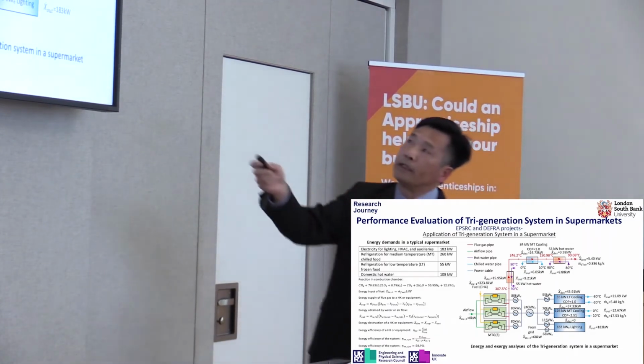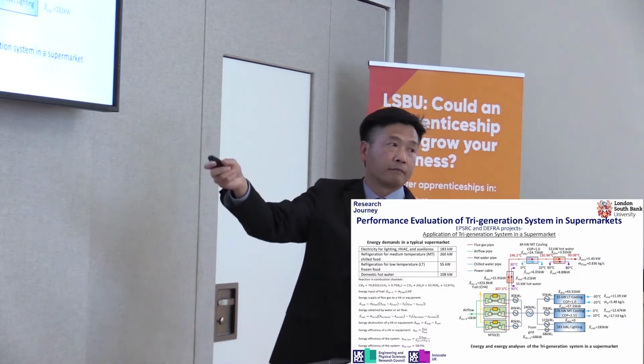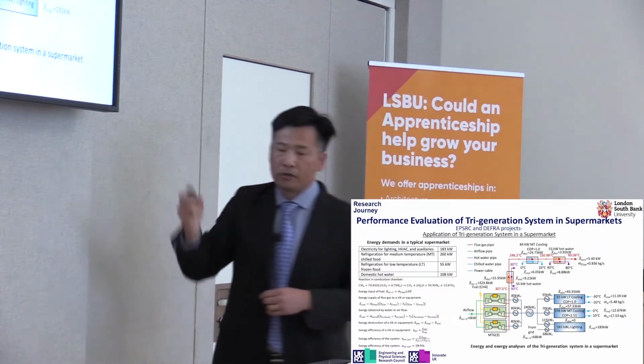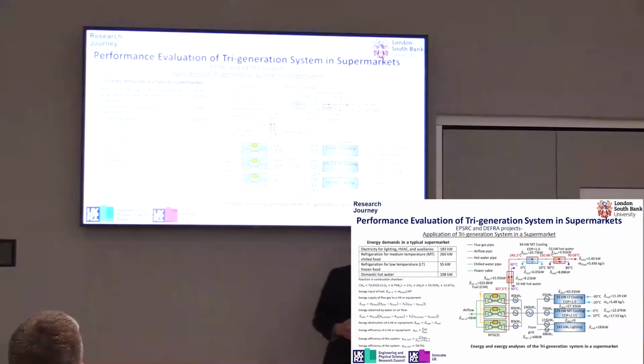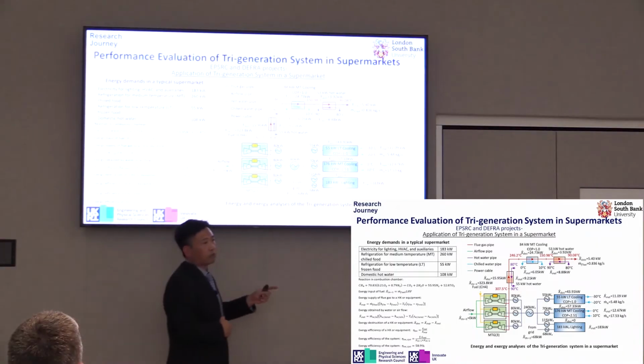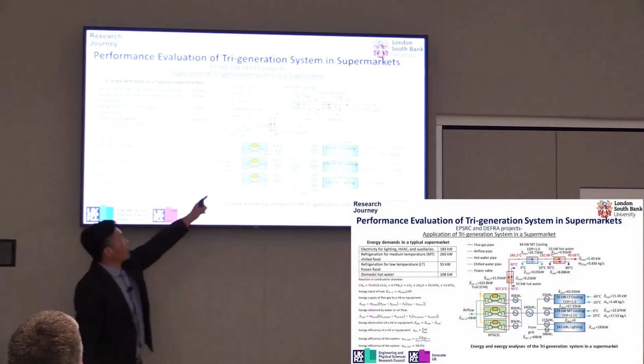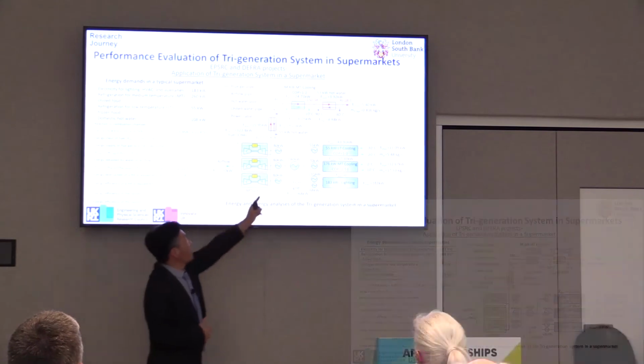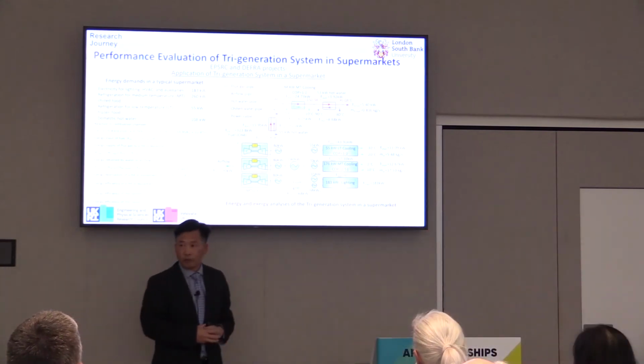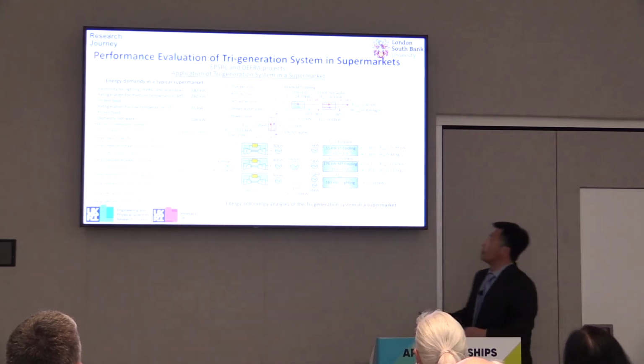So we did an initial design for this. Since each microturbine generator can generate 80 kilowatts, that is not enough for the electricity demand of the supermarket. So we select 3 microturbine generators, each generating 80 kilowatt, so together that is 240 kilowatt. So let's see how this can meet the energy demand of the supermarket.